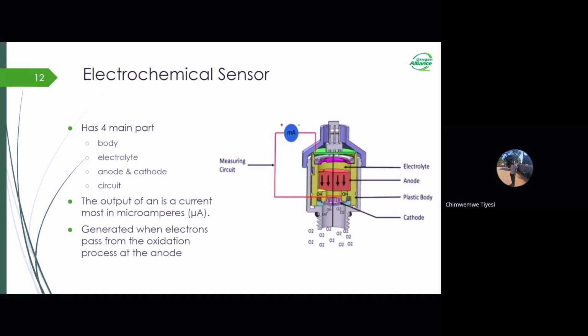and sometimes this analyzer also has a thermistor, which is used to compensate for temperature variation in the measurement of oxygen concentration. As I already mentioned, the output of this sensor is current, which is commonly measured in microamperes. This current is generated when the electrons pass through an oxidation process. Then they diffuse into the electrolyte solution to generate an electrical current, which is then used by the electrical circuit to show and display the oxygen concentration on the LCD of the oxygen analyzer that uses this electrochemical sensor.